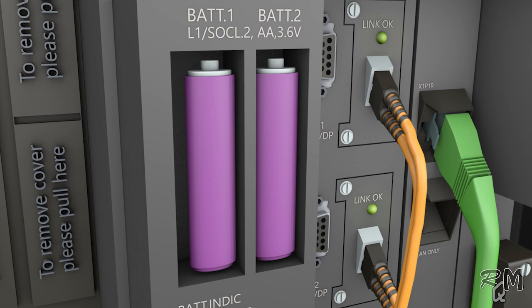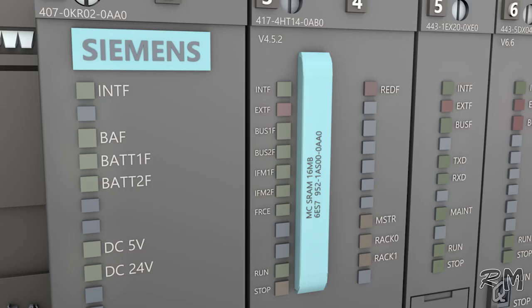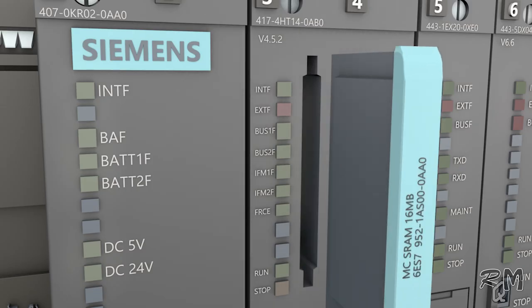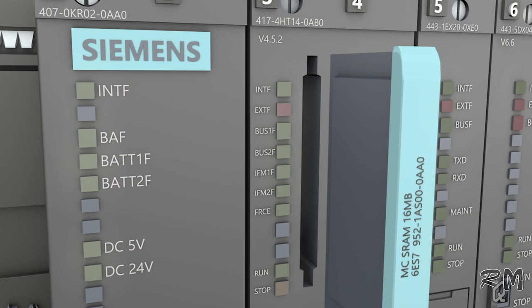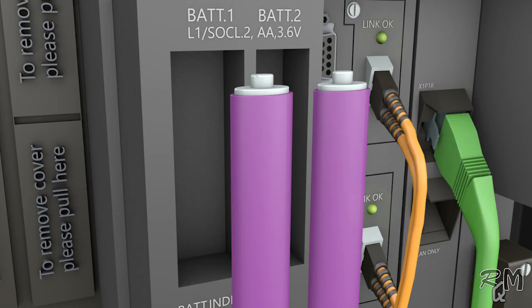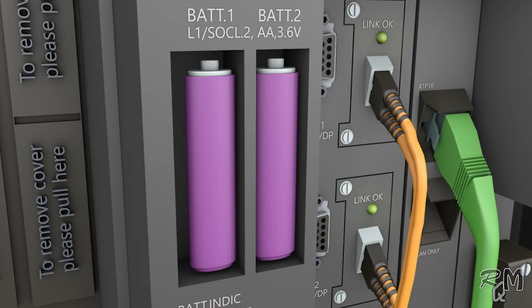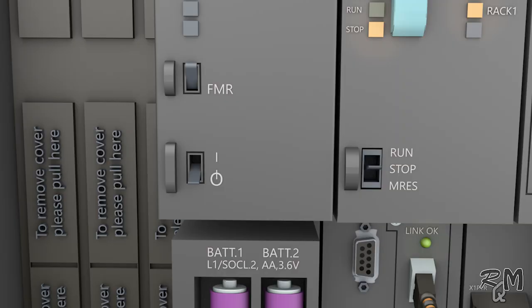Then remove backup batteries. After this if you suspect that memory card or SRAM needs replacement, then you can replace it with new one. Wait for 20 to 30 seconds. After this repeat steps backward. First insert batteries, then switch on power supply.